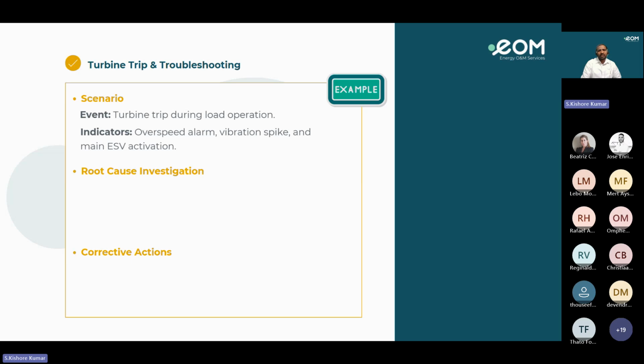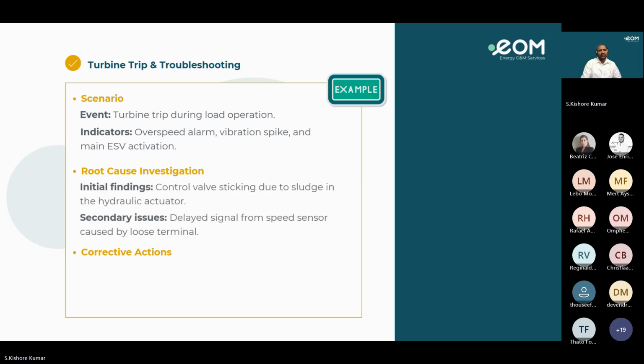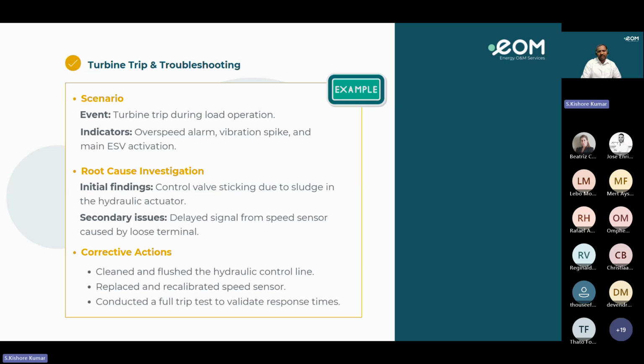The root cause analysis says: initial findings, the control valve was sticking due to sludge in the hydraulic actuator, and a secondary issue, a delayed signal from the speed sensor caused by a loose terminal. The corrective actions: cleaned and flushed the hydraulic control line, replaced and calibrated the speed sensor, and conducted a full trip test to validate response times.